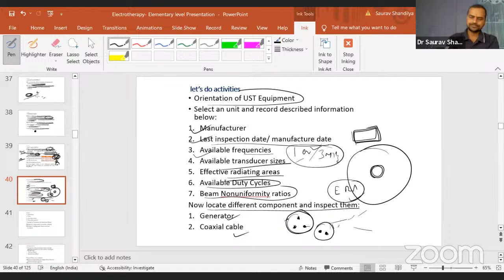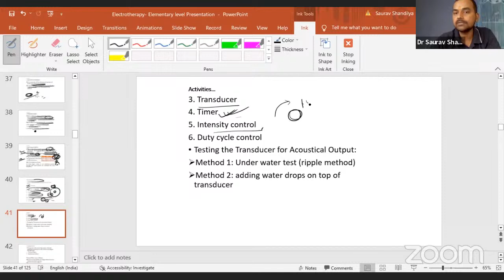Okay, after that the timer, whether it's working properly or not, you should match with your clock, office clock, or you should match with your wristwatch, and then you should do it. Then you have a timer. Timer, whether it's working or not properly, as I told you, is very important. Intensity control, whether the knob is working well or not, because suppose sometimes what happens, you are taking the knob so high, but intensity is just showing 1.5. So that also you see.